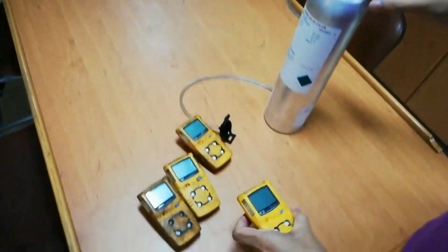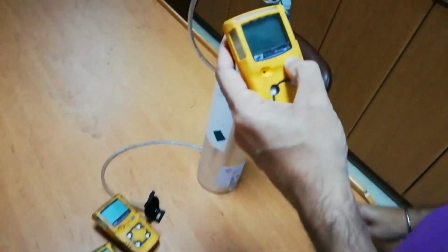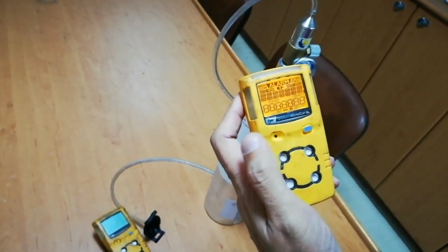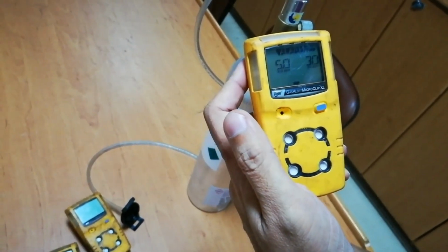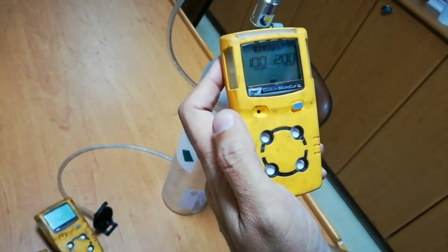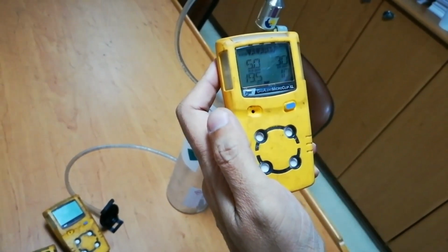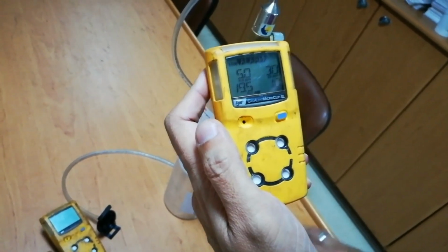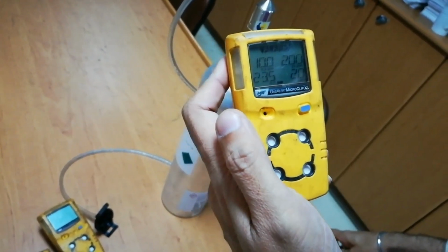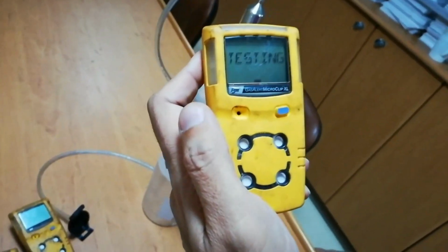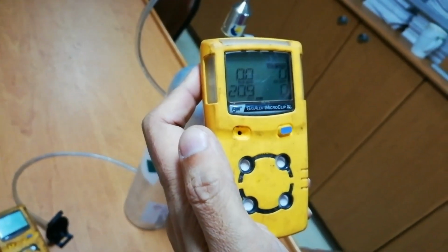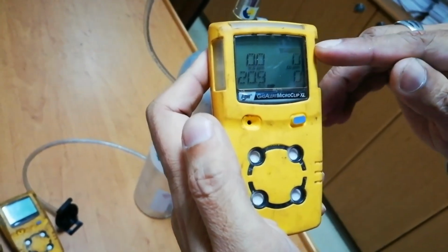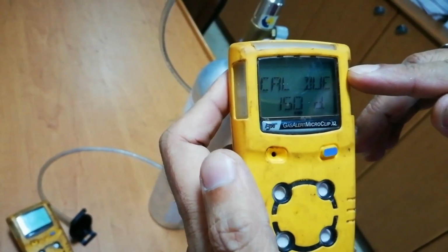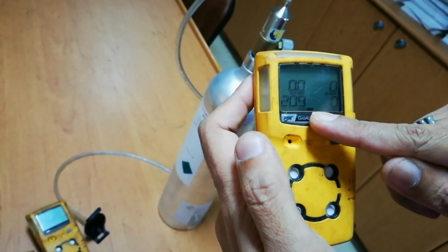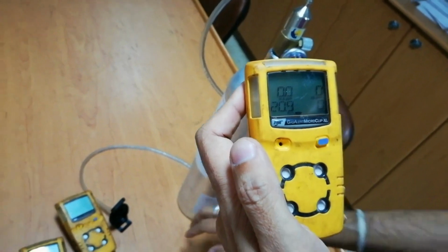First we will switch on the multi-gas detector, and once we switch on, it will do a self test by itself. Once the self test is completed, it will show the remaining days for the next calibration. Normally it shows around 180 days, but I did the calibration last month, so now you can see the remaining days for calibration is 150 days. Here we can see calibration due 150 days. So now I am going to do the calibration.